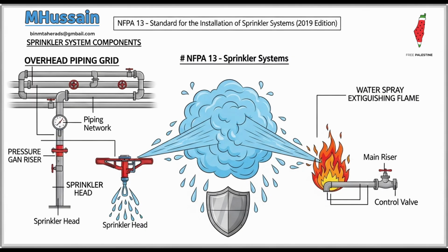Okay, so what makes it unobstructed then? Where's that dividing line drawn? Unobstructed construction is when the structural members don't materially affect that flow, and NFPA 13 gives pretty clear dimensional exceptions for this. Construction is typically considered unobstructed if the spacing of structural members, like parallel beams, exceeds 7.5 feet, that's 2.3 meters, on center. So if your beams are spaced, say, 7 feet apart, you're likely in the obstructed category, and that instantly triggers tighter, usually more expensive sprinkler spacing requirements. That 7.5-foot threshold is vital for system designers.